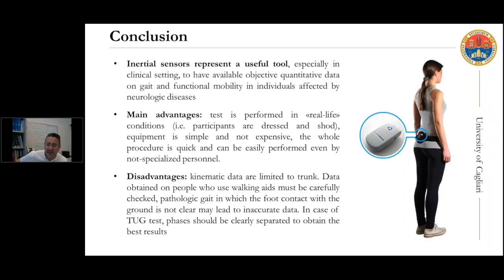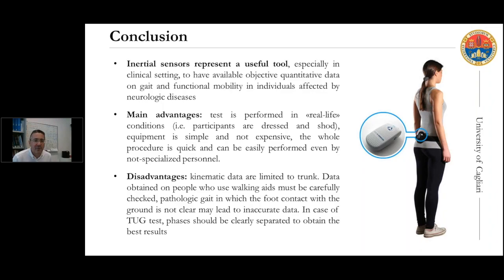Of course there are some limitations. The kinematic data are limited to the trunk, so the device is most useful for providing information about spatial-temporal parameters. Additionally, data obtained from people who use walking aids must be carefully checked, because one of the conditions for accurate data is the sensor's ability to correctly identify foot-ground contact. If this contact is not clear, data from the system report must be checked carefully. Similarly, in the case of the TUG, the phases should be clearly separated to obtain the best results. Thank you very much for your attention — if you have any questions, I'd be very glad to answer.